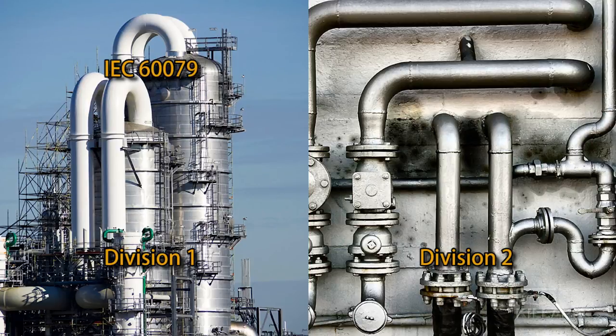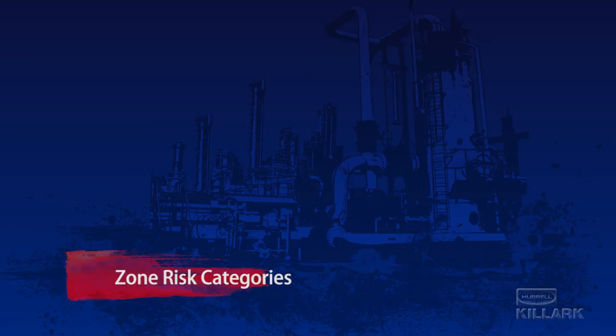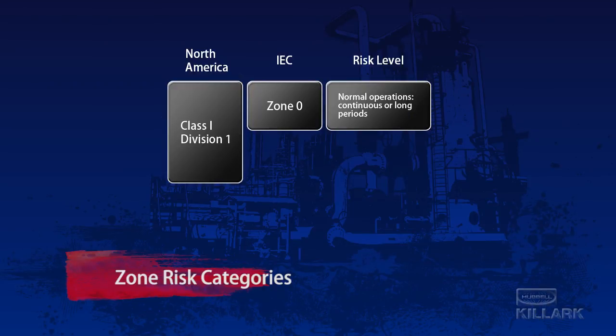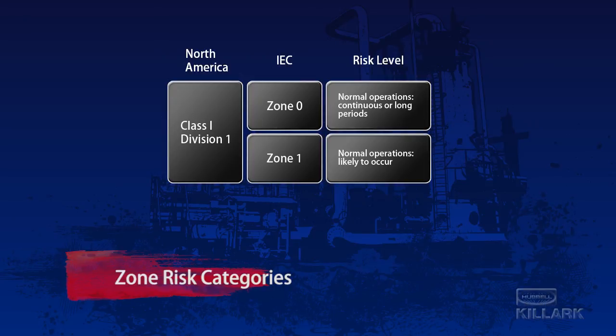IEC 60079, the principal underlying standard for harmonization, uses a similar concept for categorizing risks, but it splits the risk of ignitable mixtures during normal operations into two separate categories. Calling the categories zones, the IEC approach starts with Zone 0, defined as those locations operating normally that could create ignitable concentrations of gases or vapors continuously or for long periods of time. Secondly, there is Zone 1. This zone could still be expected to create explosive concentrations during normal operations, but not often enough or long enough to require a Zone 0 designation.